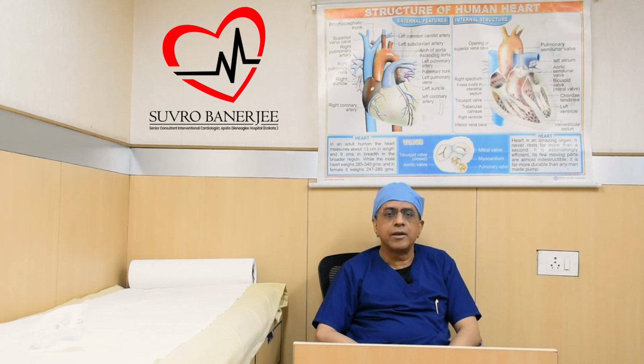it does not cause much problem. But if you are doing a vigorous activity, normally your heart rate would go up. But if you have a fixed pacemaker which is not responsive, then the heart rate would remain 60 or 70 even when you are exerting yourself, and in such cases you may start becoming short of breath. But rate responsive pacemakers have sensors inbuilt which would detect that you are exercising and would automatically increase the pacemaker rate so that you do not get short of breath. Nowadays most of these pacemakers are rate responsive, so hardly are there any pacemakers which are not.